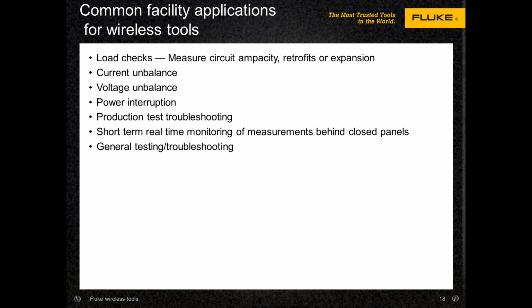Right. So a lot of these conveniences are typically new things. The wireless concept itself has enabled users to do things a lot easier, a lot faster, and a lot safer. So let's talk about some common facility applications for wireless tools and where the wireless stuff really shines. In the case of things like load checks, for instance, if you're on a branch circuit in a facility and you need to add a new system to that facility, you need to determine whether you have enough capacity in that circuit to add that equipment, or do you need to pull a new circuit.